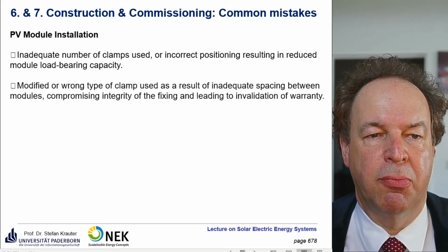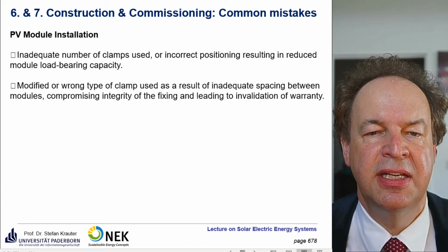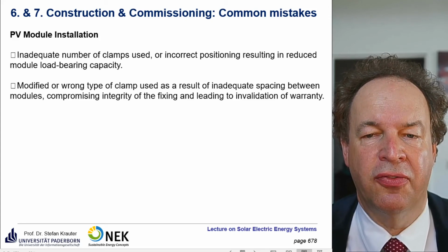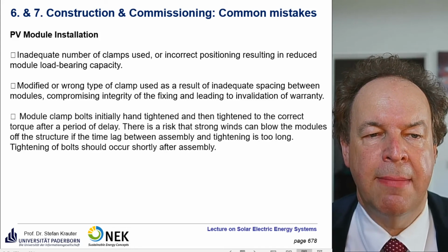This is what I mentioned. So modified or wrong type of clamps. So there could be inadequate spacing between the modules, compromising the integrity of the fixing and leading to invalidation of the warranty.